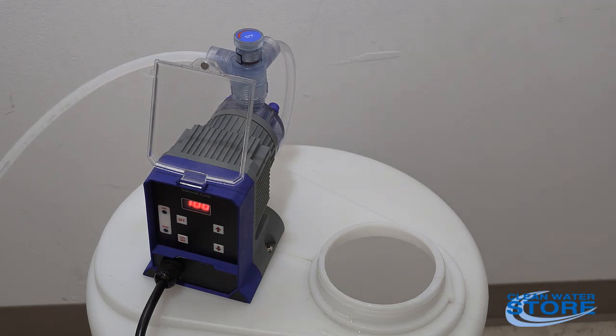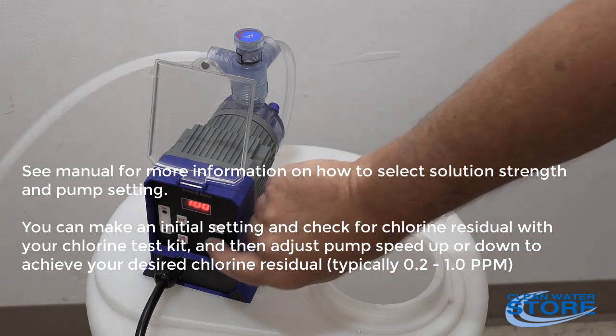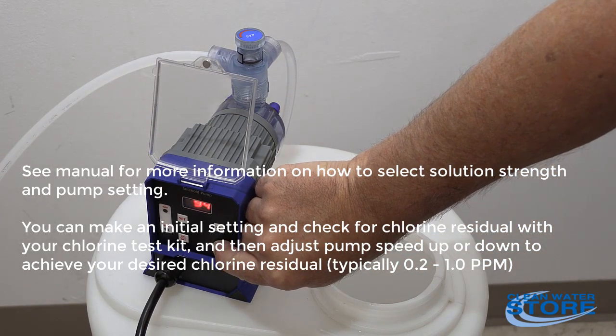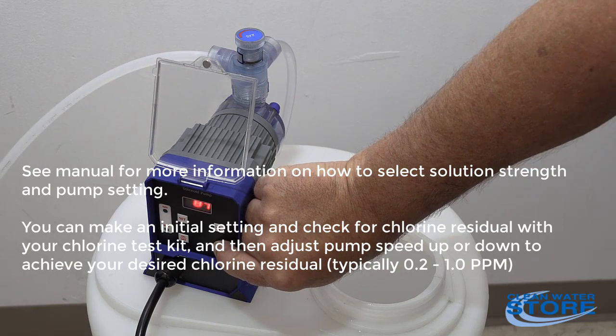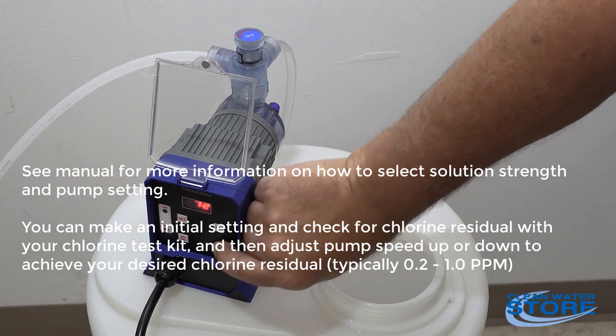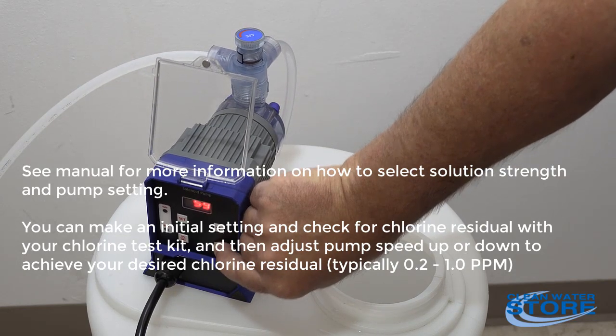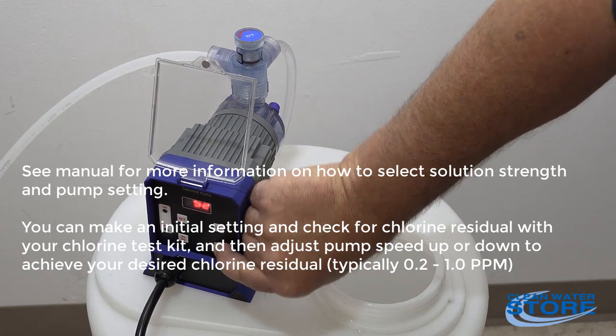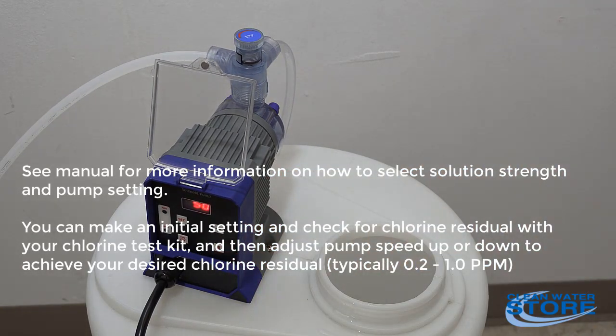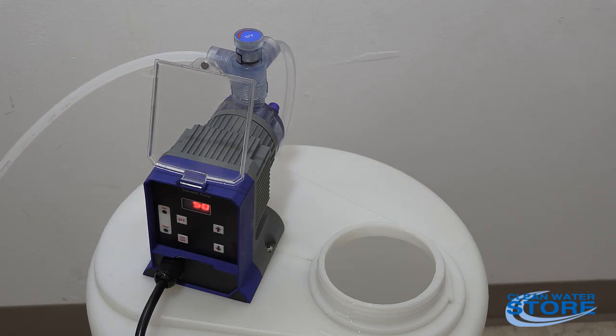At that point, once you get your solution in there, you're going to go ahead and adjust this down to 50%. And 50% is about where you're going to want to be if your well is producing between 5 and 15 gallons a minute. So set that at 50%, go ahead and run it for a bit, and then go ahead and follow your startup guide. Check your free chlorine. Get that somewhere between 0.2 and 0.4 ppm, and you will be good to go.